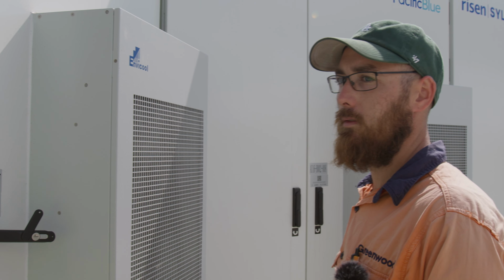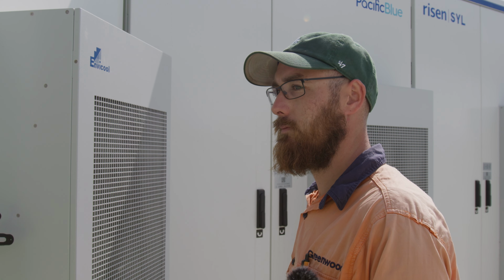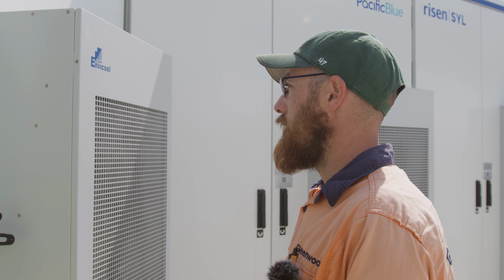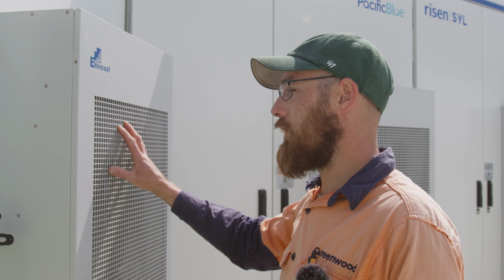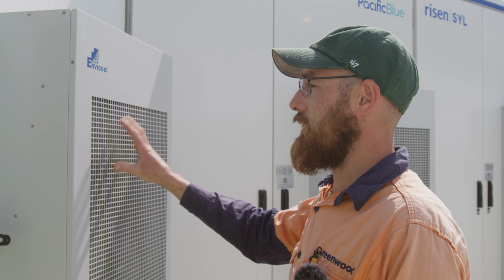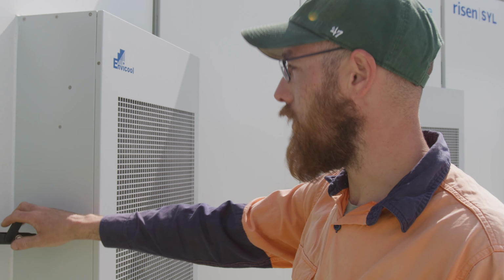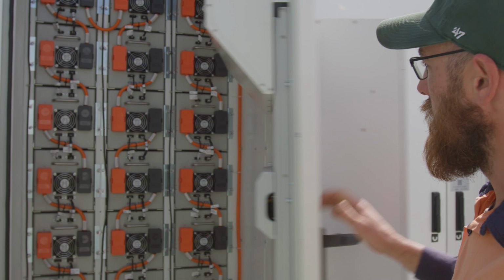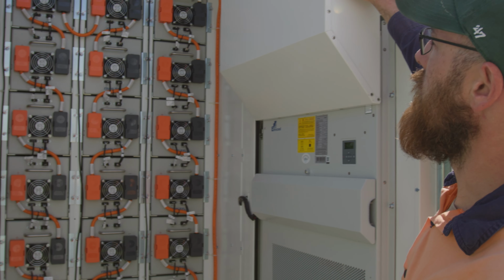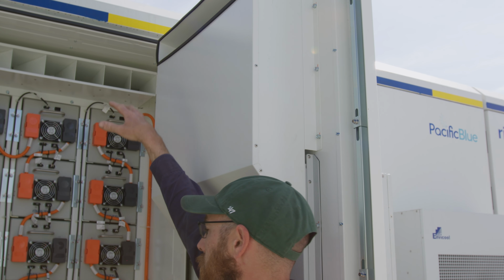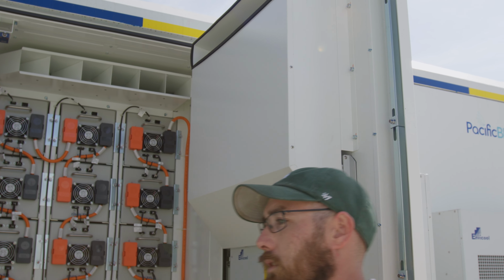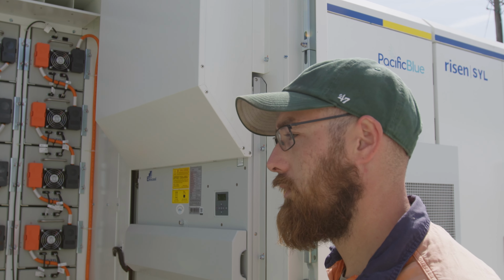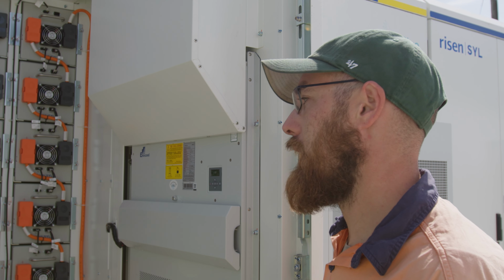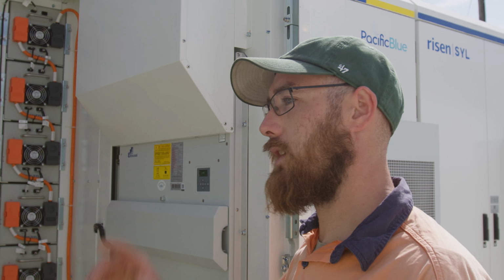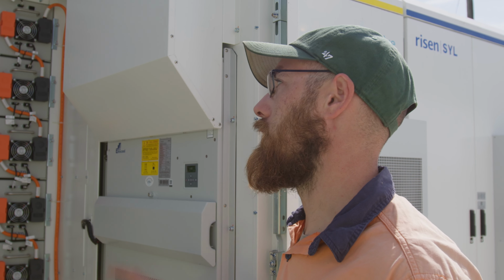So you were mentioning before, Alex, about the actual HVAC, and from a design perspective, can you elaborate there? Yeah, it's really one of the only locations you could put it on this unit, but it does hang off the door. So this is the HVAC unit for this battery, and it will circulate air through this duct, into that duct, and then down around all the cells. Couldn't it have been put on the back of the unit? It could, but the back of the unit is reserved for servicing. There are screws on the back to remove to get to the back of the system.